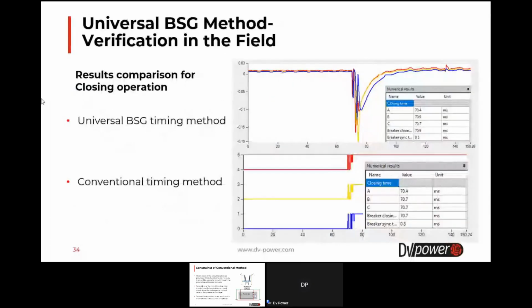Here are compared numerical and graphical results for the closing operation between the universal BSG timing method and the conventional timing method. As you can see, closing time is around 70 milliseconds. There is a very small deviation between these two methods. So this way we verified that this universal BSG timing method works correctly.